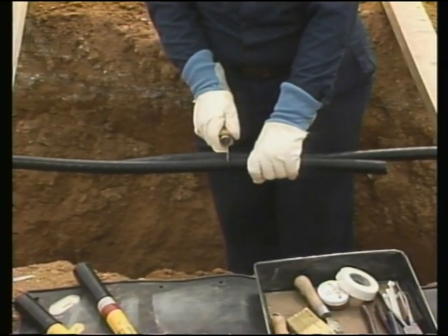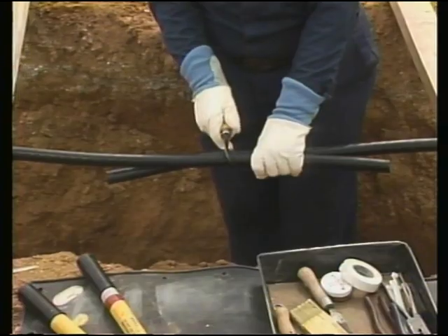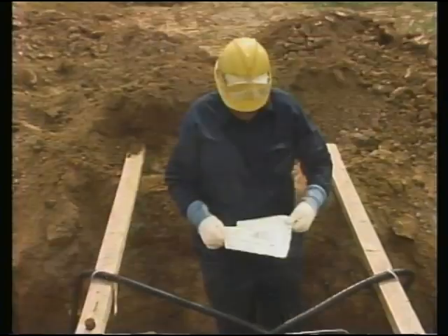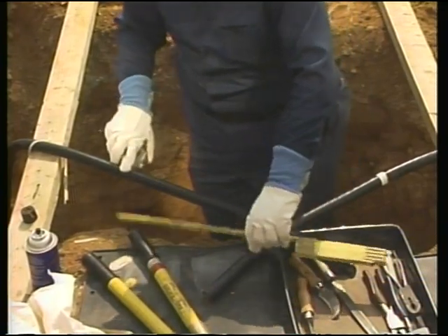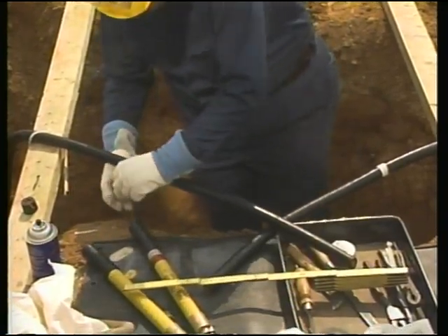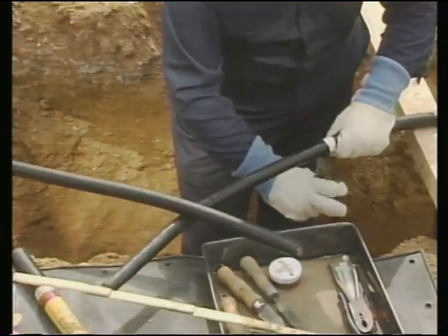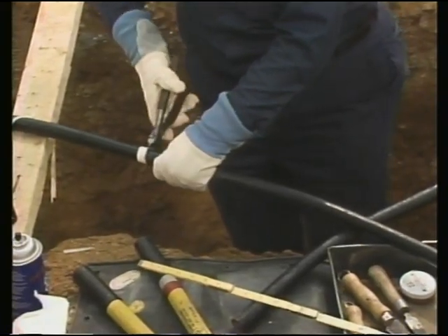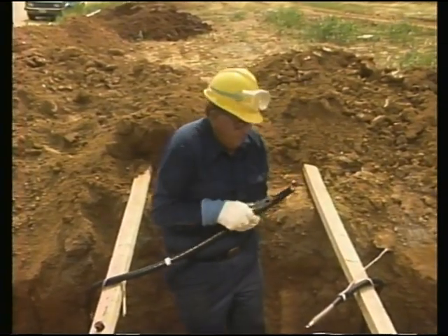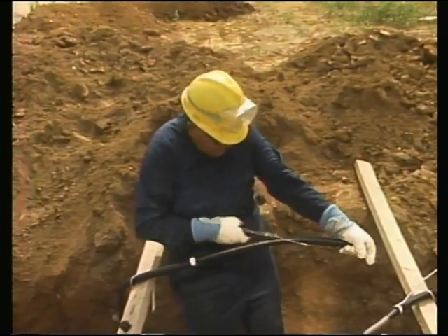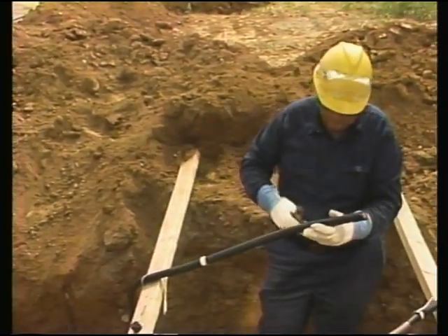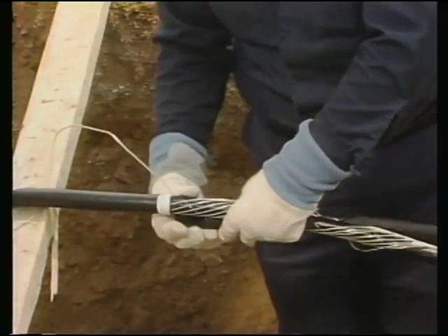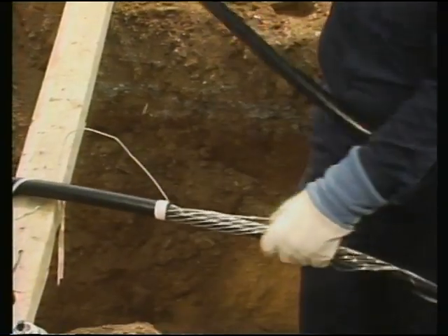If there's no slack and the cables can't be overlapped, additional concentric wiring may have to be spliced to the existing wires. Following the directions, a measurement is then taken from the center line and marked on each cable. Then the workman lightly scores the cables, making sure not to damage the concentric wires. Then a single strand of the cable's concentric shield is stripped back to make removing the cable jacket easier. The cable jacket is then peeled back carefully and removed down to the mark the workman had made earlier.